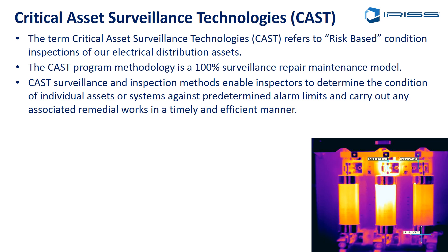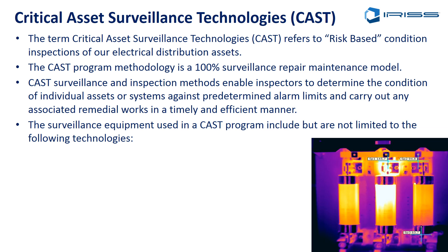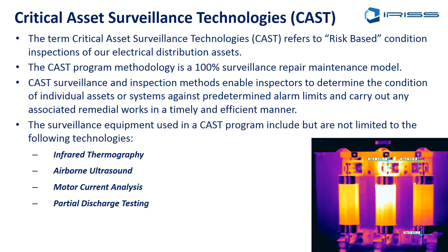We are going to act on the results from the surveillance of the equipment and not on calendar-based maintenance. The surveillance equipment used in the CAST program includes infrared thermography, airborne ultrasound, partial discharge testing, motor current analysis, UV or corona cameras, and most importantly, the visual inspection.